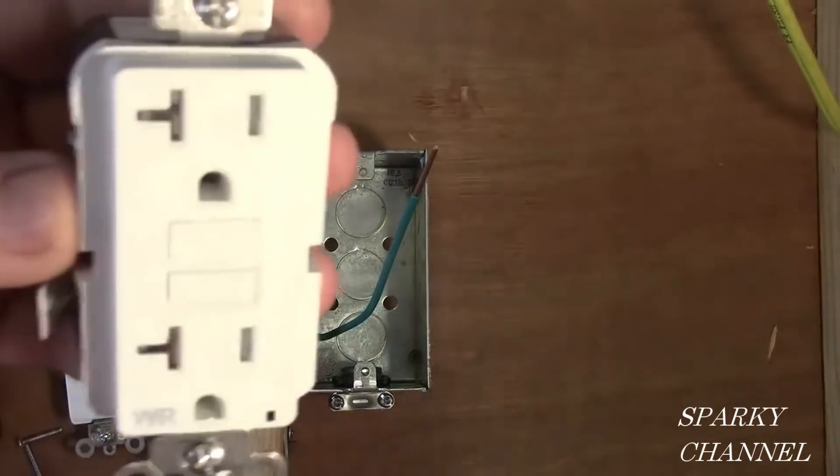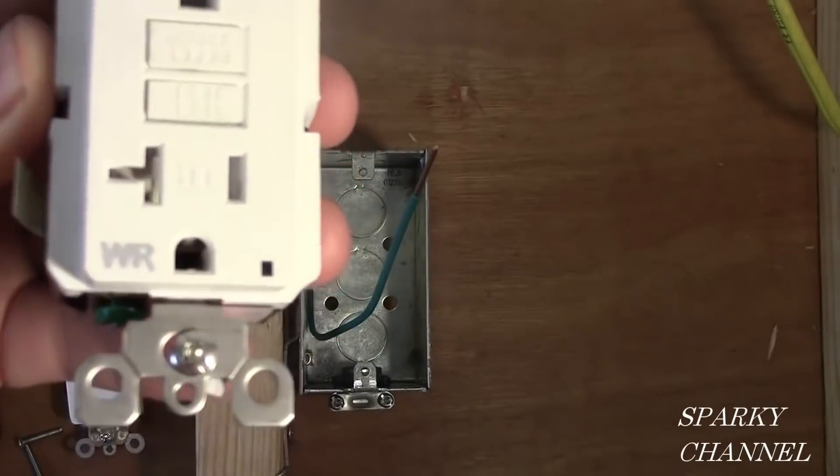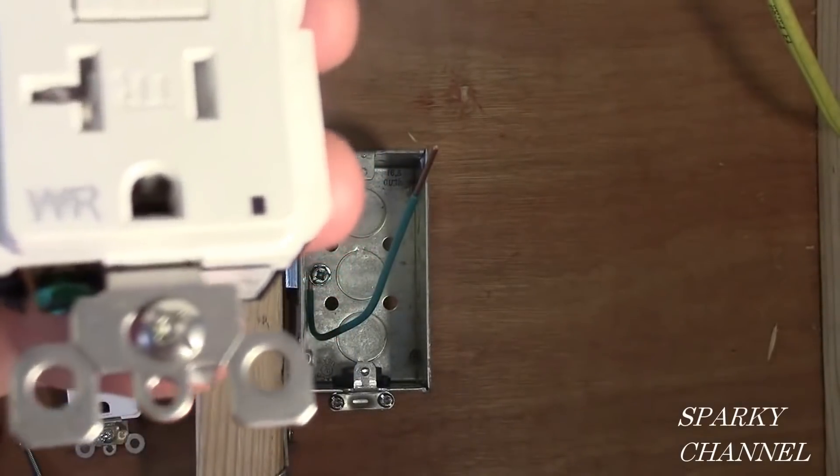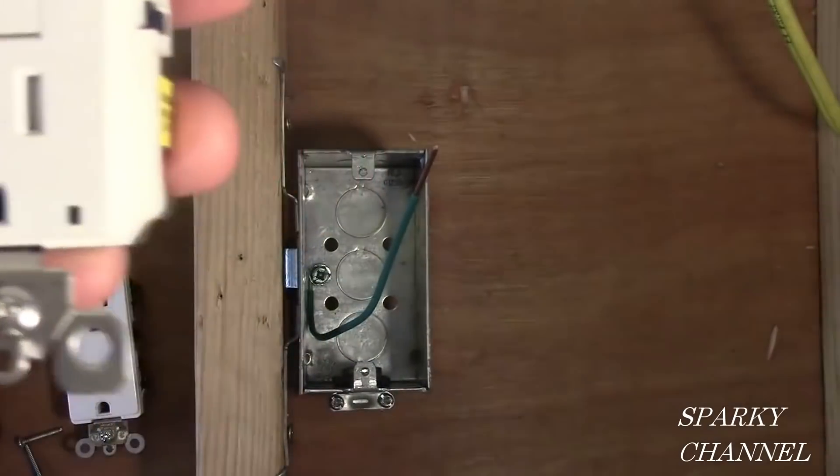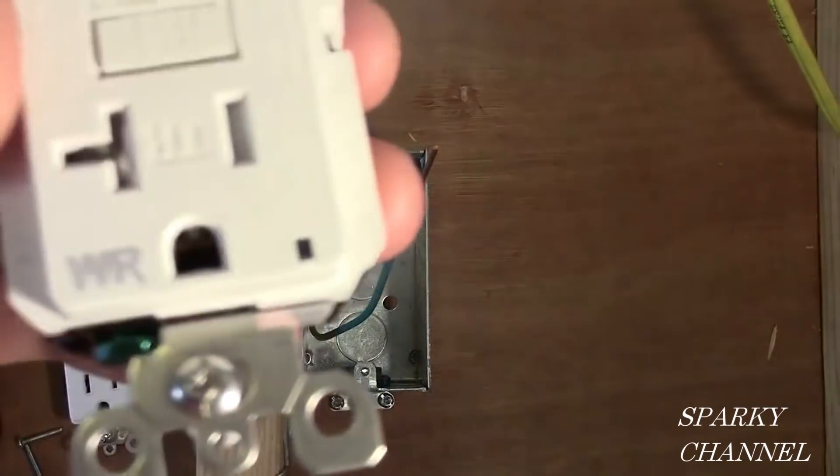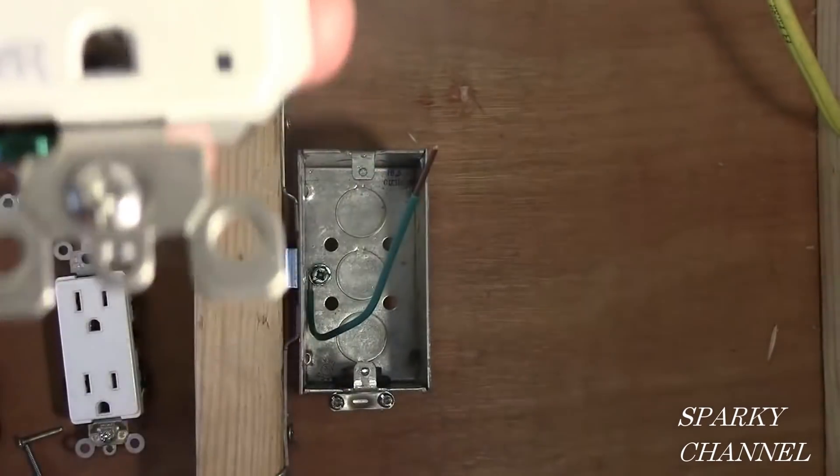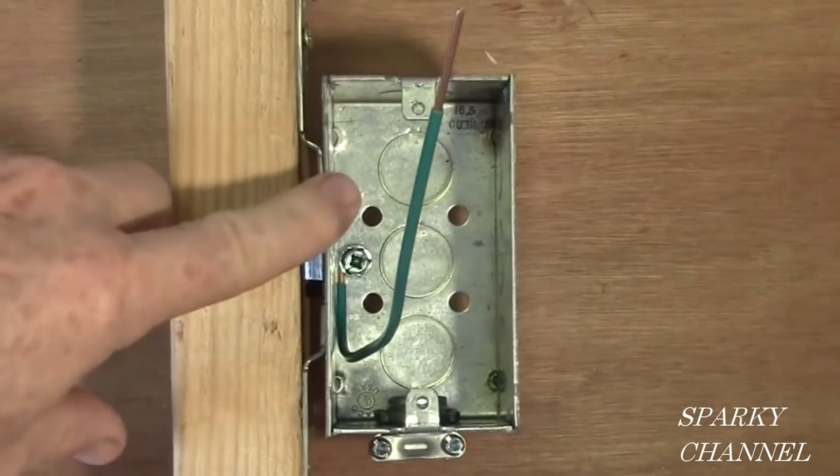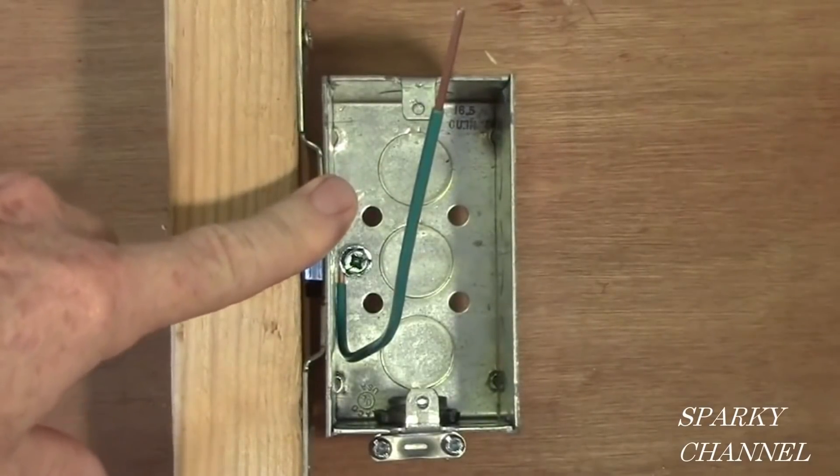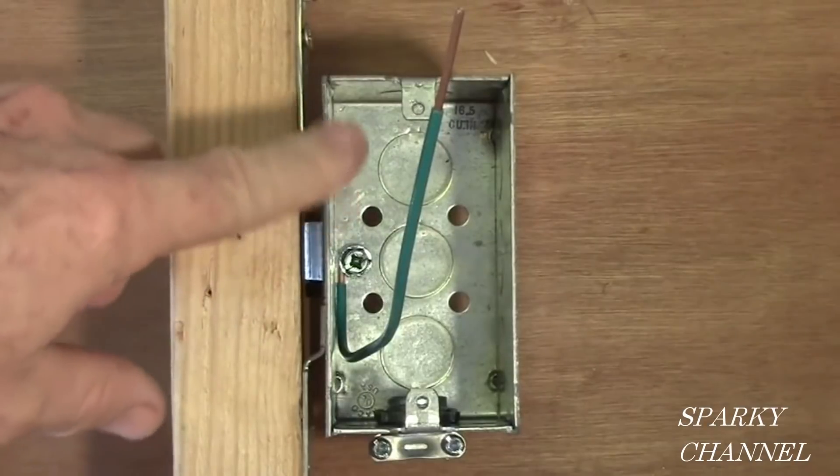This is a 20 amp GFCI weather resistant, and you'll notice it doesn't have one. So some of them do have the self-grounding clips and some of them don't. When you connect your metal box to the ground system for your house, that's called bonding.